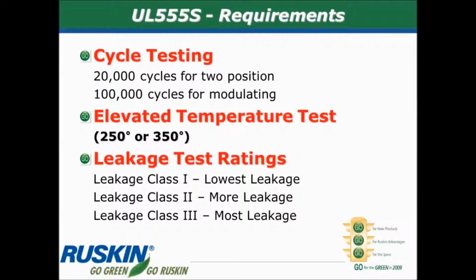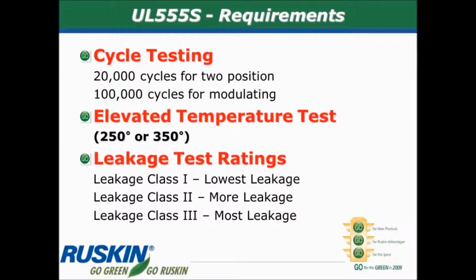The UL 555S testing to get rated to be a valid smoke damper is pretty stringent. If the damper is designed to be two-position, just open or close, it must be cycle tested 20,000 times. It has to successfully complete 20,000 cycles in order to pass the test. Now, if the damper is one of the new style modulating smoke dampers, where it has a modulating actuator that allows it to operate as a control damper, in addition to being a smoke damper, that product has to be cycle tested 100,000 times in order to pass the test. So when these dampers are manufactured and shipped and installed, you know that they're going to work because they've passed really, really tough testing. The dampers have to be tested with elevated temperatures, rated for either 250 degrees Fahrenheit or 350. And the dampers have the leakage rating we just discussed earlier.